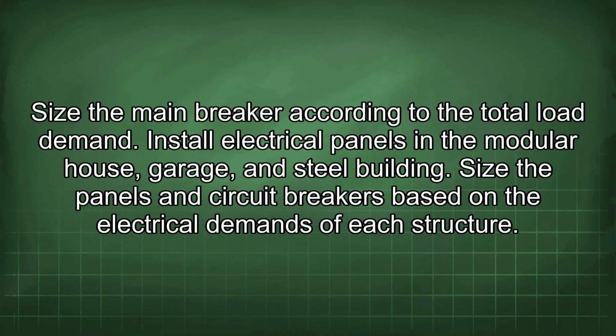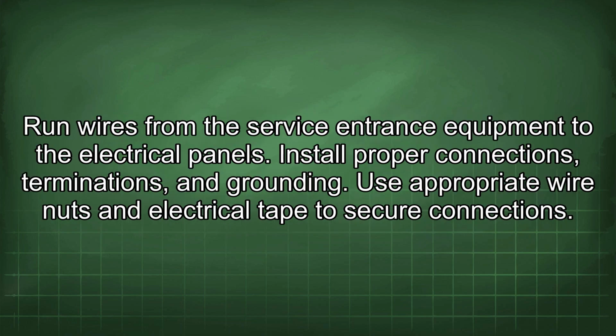Install electrical panels in the modular house, garage, and steel building. Size the panels and circuit breakers based on the electrical demands of each structure. Run wires from the service entrance equipment to the electrical panels. Install proper connections, terminations, and grounding. Use appropriate wire nuts and electrical tape to secure connections.